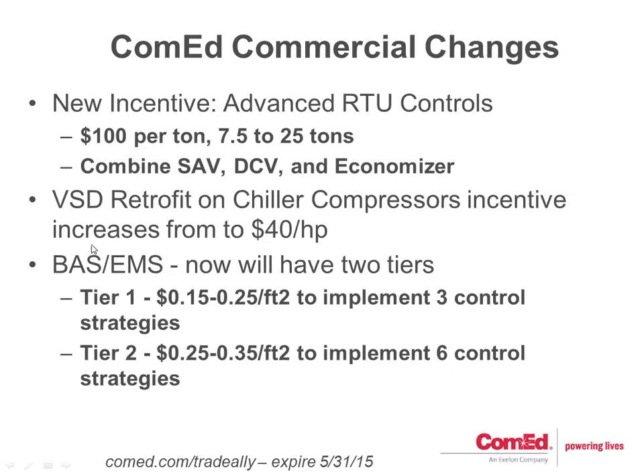Okay. All right, on the ComEd side of the equation, which is the electric side, there are a couple new rebates. There's one for advanced RTU controls. This is $100 per ton, and it's for units that range between 7.5 and 25 tons. What you're doing is combining staged air volume, where we put a VFD on the rooftop unit and use it to control different air speeds to match different stages of cooling. You're putting DCV, demand control ventilation CO2 sensors on there, and you're putting economizers on the rooftop. So if you're doing those three things, you can get $100 per ton.